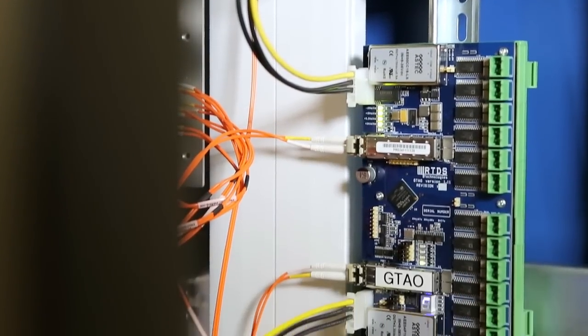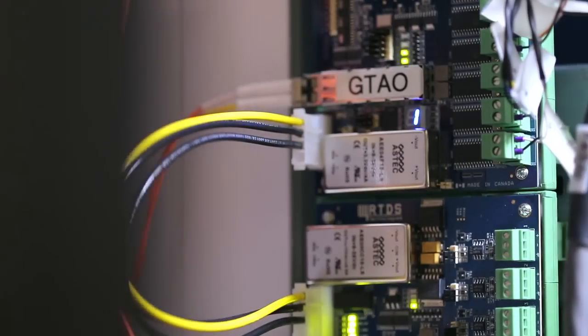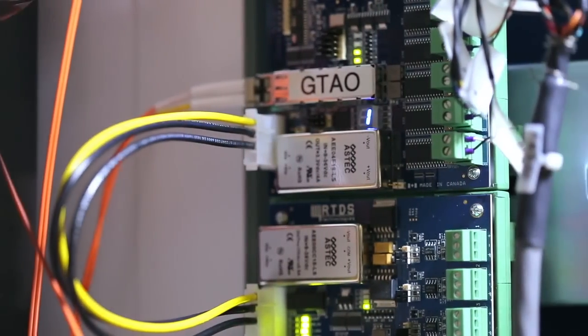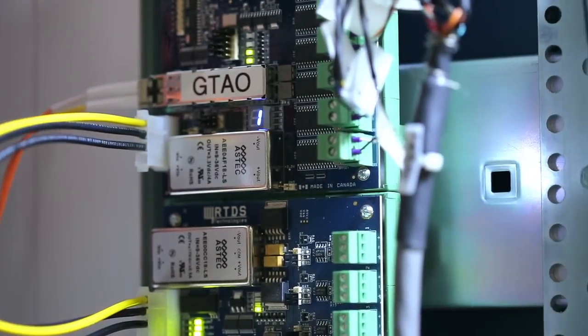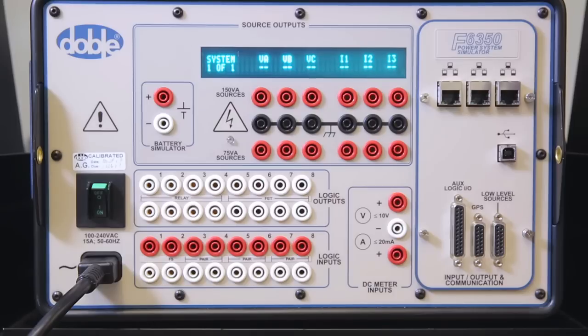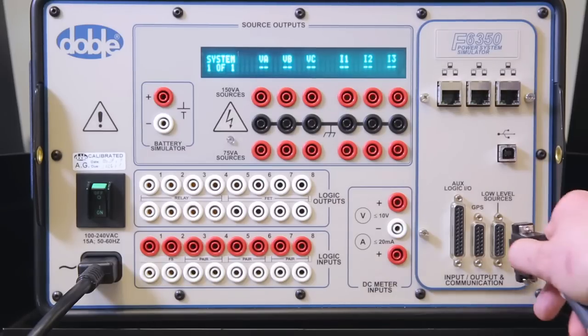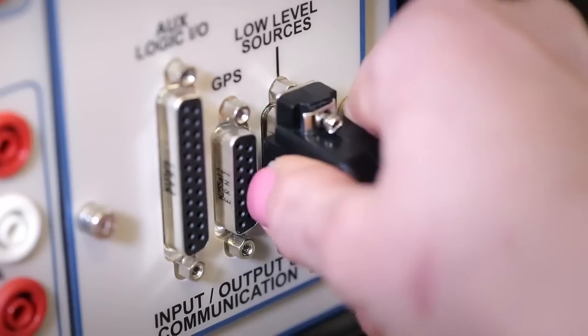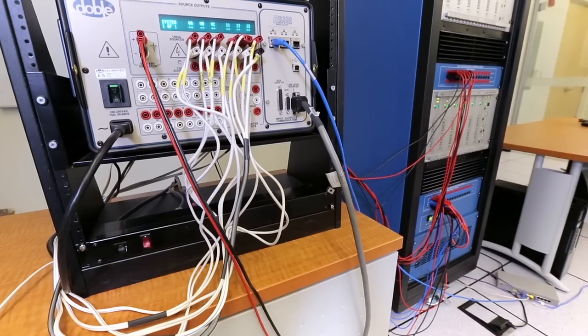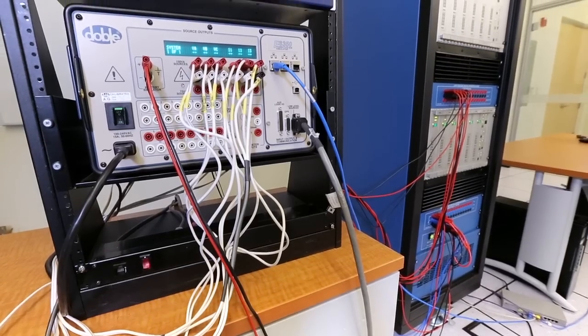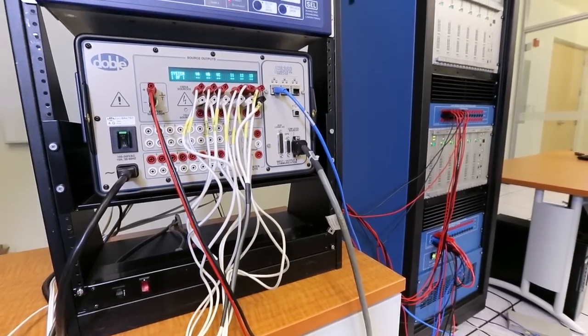The GTAO card has a maximum output range of plus or minus 10 volts peak. A power amplifier is used to scale up the output waveform and test the relay using its in-service operating voltages and currents.